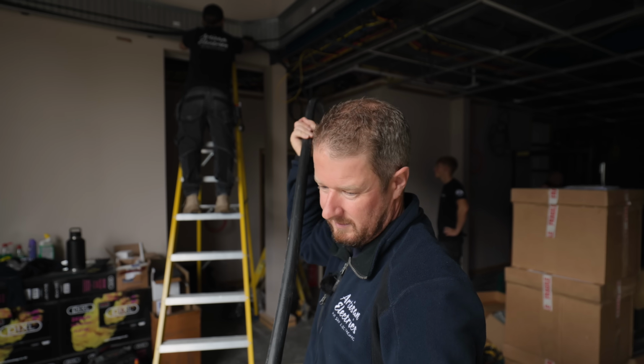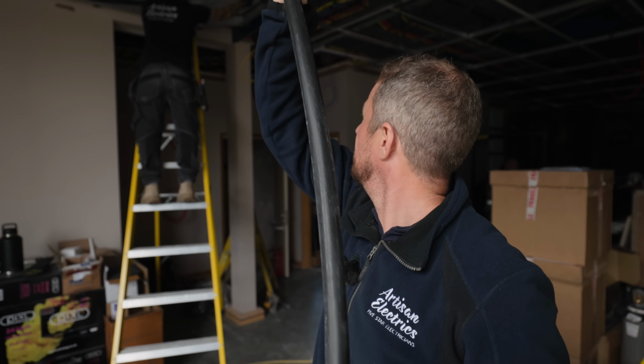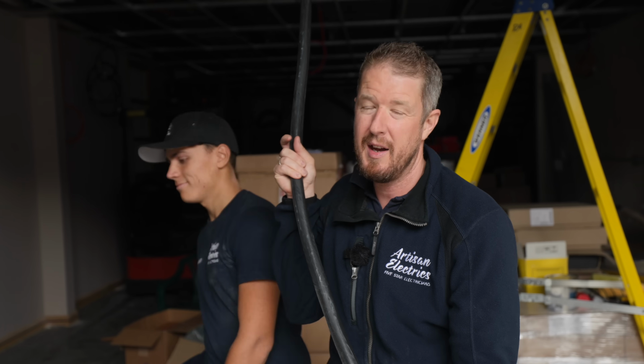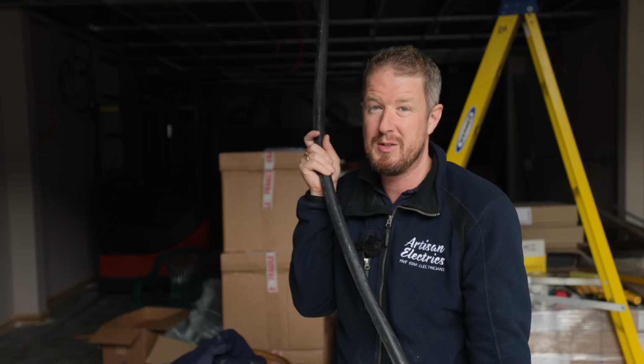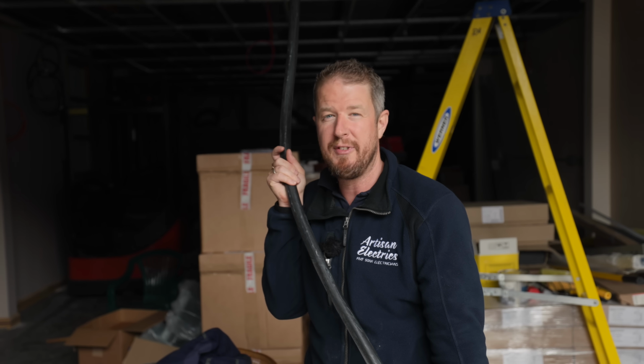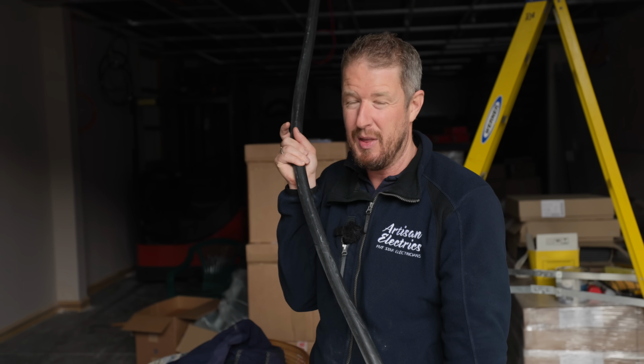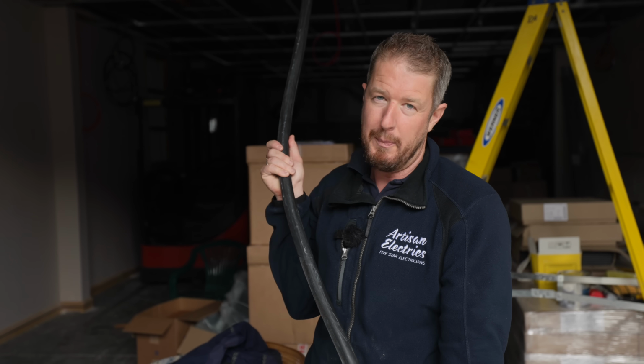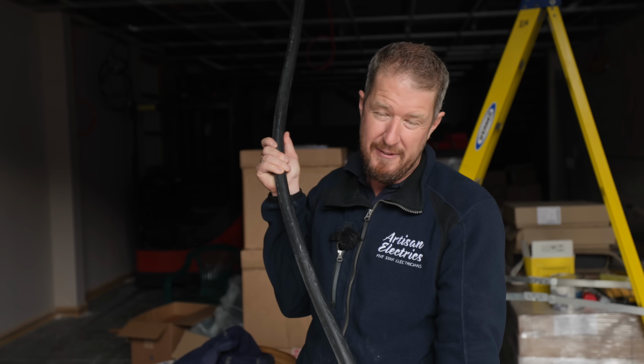So this is actually 35mm 4-core steel wire armoured from Doncaster Cables. The reason we're using 35, even though it's a little bit overkill, is because of the length. We just want to avoid voltage drop for the property, and the fact that the power for the entire building is going through this cable, although it's a 100 amp supply, so 25 would be fine.